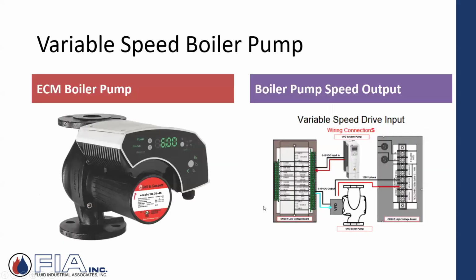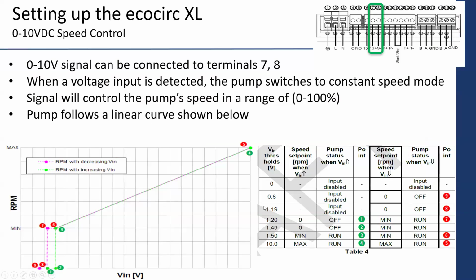Very specifically, it's for boilers. I get into some big BTU condensing boilers that can modulate their firing rate. So at 100% fire, I want 100% flow across that heat exchanger. But as the building system conditions change and the modulation starts to reduce, why? Because I want to save gas consumption because the load's not that great. In parallel, why don't I save the flow rate across that heat exchanger? Instead of keeping it full flow with a reduced modulation, I now have technology that can respond to that. So I have onboard smart that can take this 0 to 10 or 4 to 20.